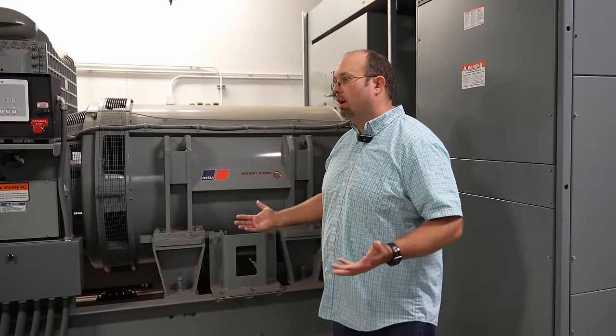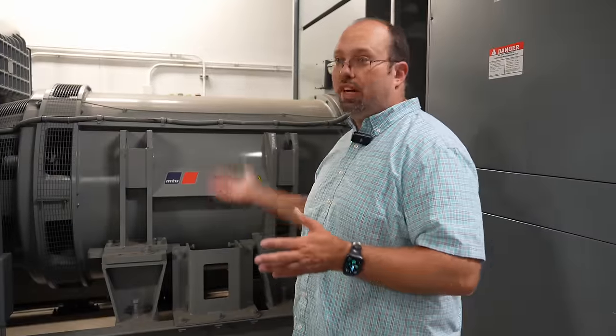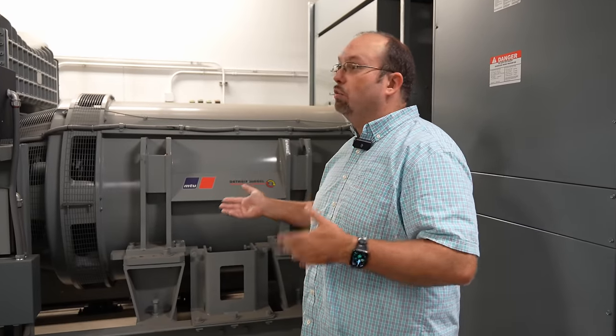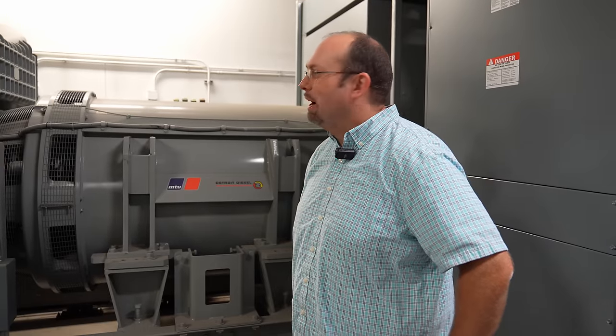When you're dealing with a facility that ranges from a couple of megawatts up to dozens of megawatts, one generator isn't enough. So you have busing or paralleling equipment. If the first generator attaches to the bus with a bad waveform, it can set a bad standard. When the second generator tries to latch on and can't match that standard, it fails to connect — and you could end up with only one of your seven generators attached. You can't run an entire data center on one-seventh of your critical power generation.